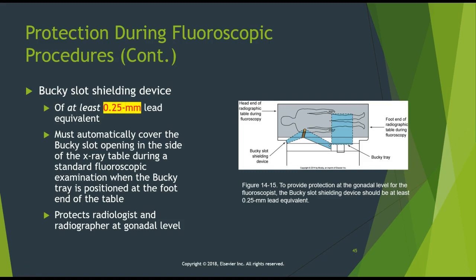This equivalent should be 0.25 millimeter lead as well. And what this does is when you're fluoroing, it takes this Bucky slot shielding device, covers that opening up and protects you and the radiologist and anyone else helping out in the room. And without this device and without the protective curtain in place, the exposure rate for the radiologist doing the fluoro would exceed 1 milligray per hour at a distance of 0.6 meters from that side of the X-ray table, so it makes a difference in your dose.